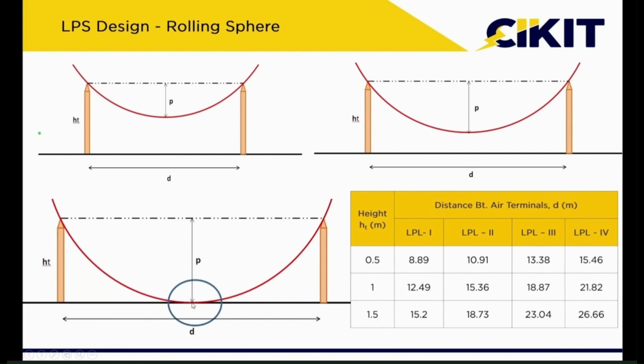So if the sphere is making contact with the structure, then it means that the penetration distance is equal to the height of the air terminals. If the penetration distance and the height are equal, then the sphere will be making contact. So, if we want the sphere not to make contact with this particular structure, then we should ensure that the penetration distance is always lesser than the height of the air terminal. So, we have performed the calculation and we have shown these distances for different heights and for different levels.